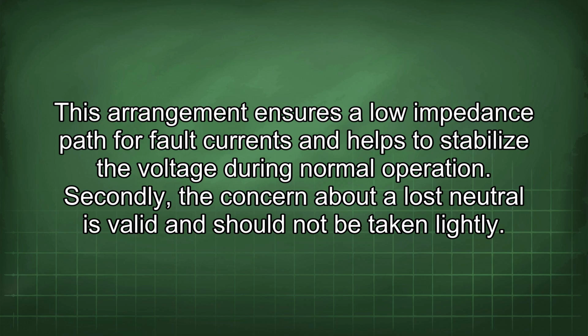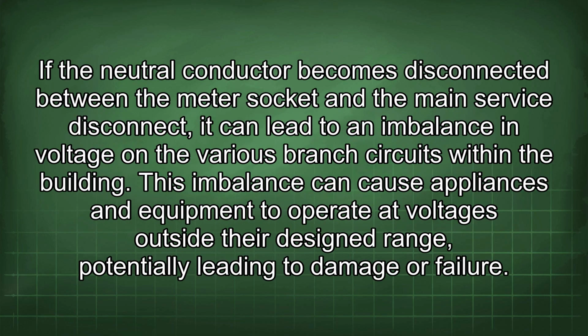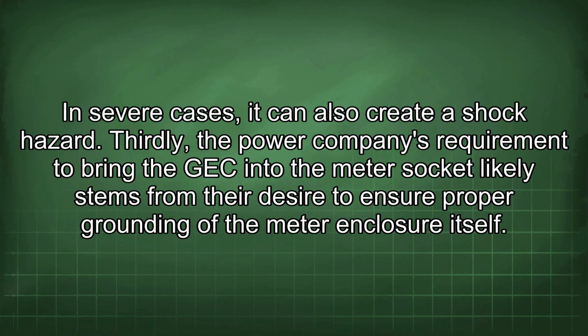Secondly, the concern about a lost neutral is valid and should not be taken lightly. If the neutral conductor becomes disconnected between the meter socket and the main service disconnect, it can lead to an imbalance in voltage on the various branch circuits within the building. This imbalance can cause appliances and equipment to operate at voltages outside their designed range, potentially leading to damage or failure. In severe cases, it can also create a shock hazard.